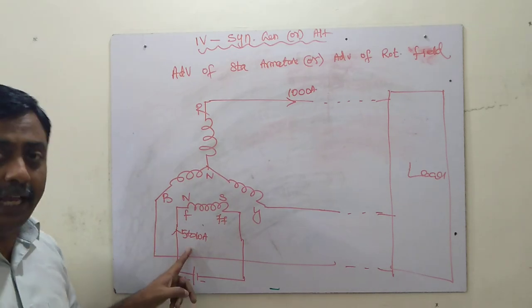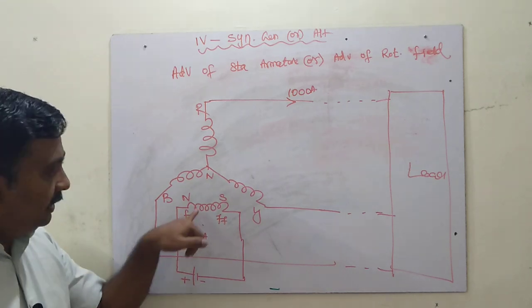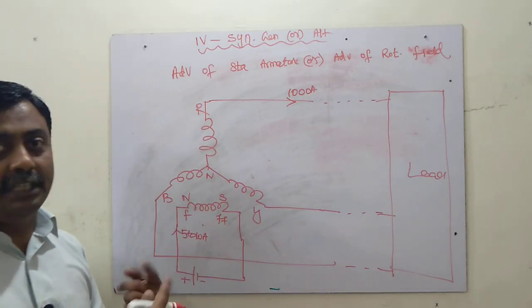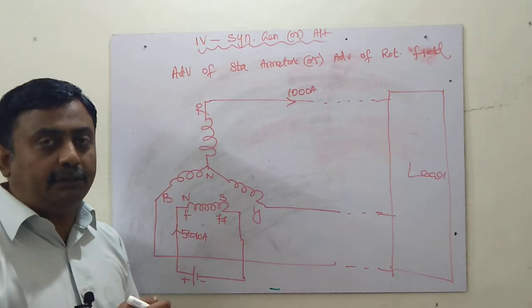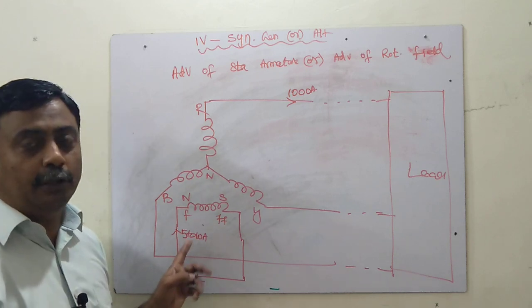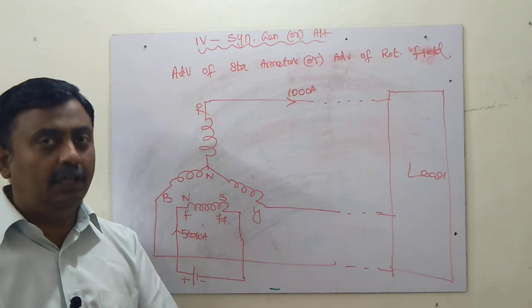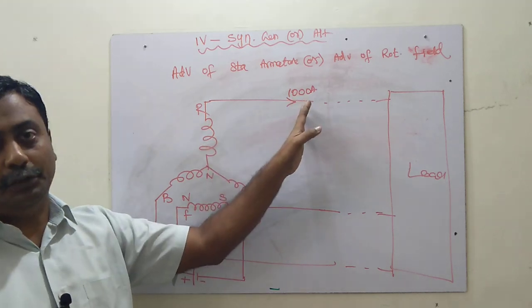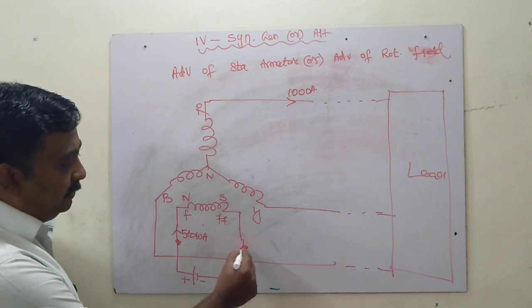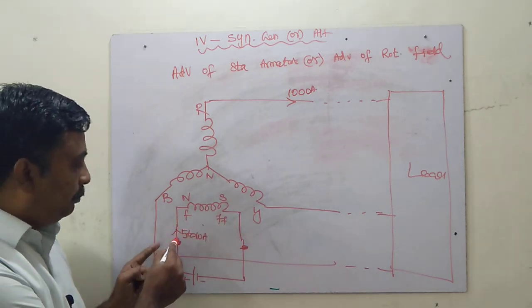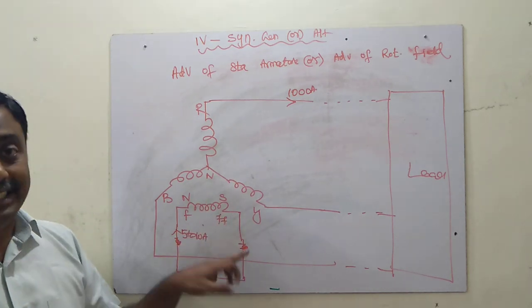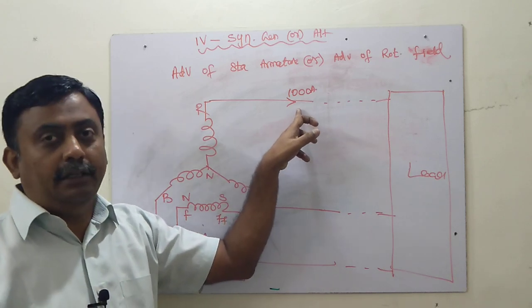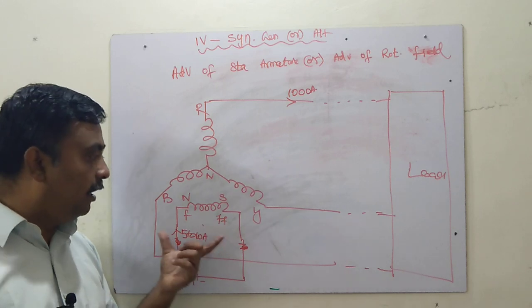If the armature is rotating, we cannot directly tap the energy; we need slip rings and brushes. For such high current, the sparking would be severe. Instead, by making the field the rotating part and giving it only 5 amps via slip rings and brushes, the slip ring and brush assembly size will be small and sparking will be minimal. That is the main reason we go for a stationary armature.